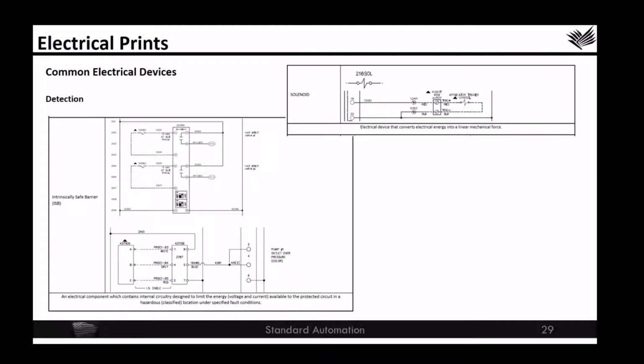We also have intrinsically safe barriers. Intrinsically safe barriers are electrical components which contain internal circuitry designed to limit the energy available to the protected circuit in the hazardous location under the specified fault conditions. So in a painting environment, there are certain current and voltage limitations allowed in that environment to keep it explosion proof. And if a device is rated for more than that voltage and current, then it's got to pass through an ISB, or intrinsically safe barrier, to make sure that the energy going out to the device is limited and stays within specification.